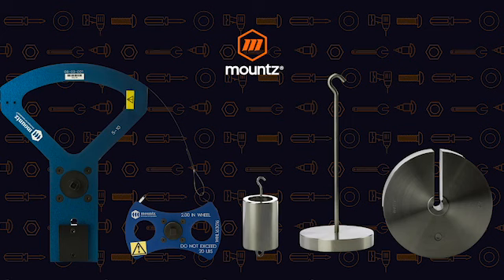So as we look at our demo for today, we have a 2-foot segment arm that is going to be measuring a 200 foot-pound sensor. And to do that, to get to 10%, 50%, and 100%, we'll basically use half of the weight that you would, because of the length of arm. So at 10%, we would be using a 5-pound weight, which is going to give us 10%, and a 10-pound weight, which is going to give us our 20% value, and so on as we move through the actual percentage.